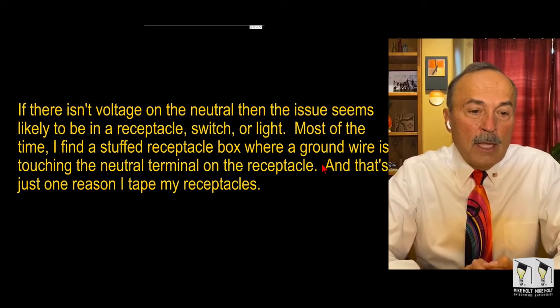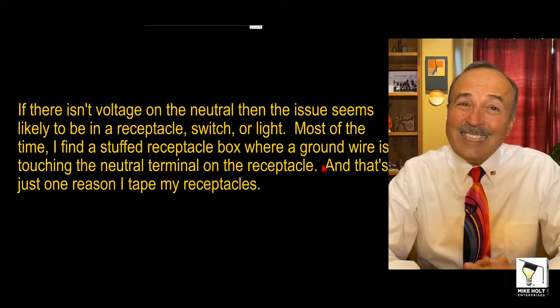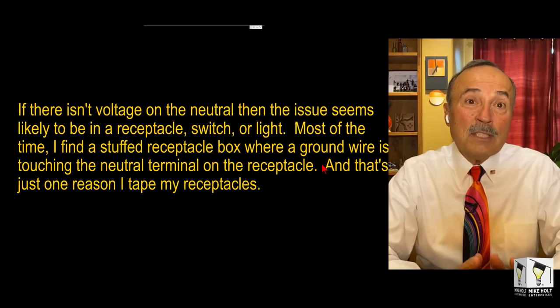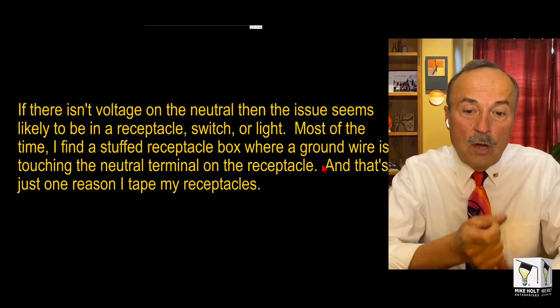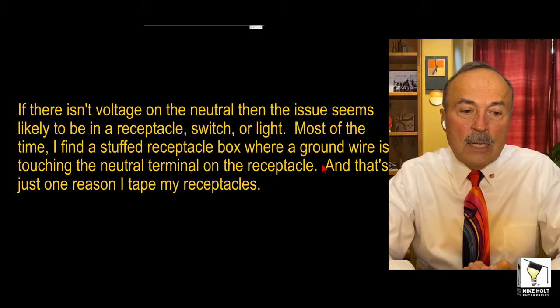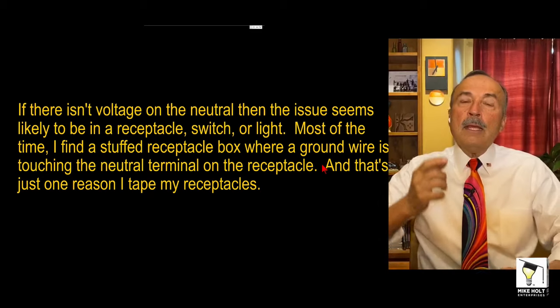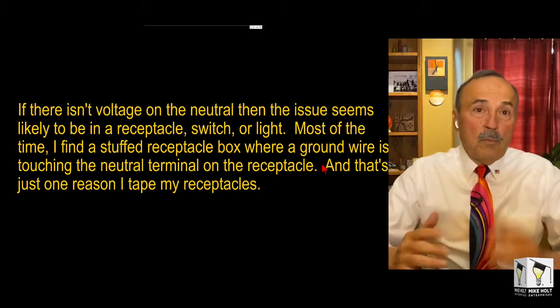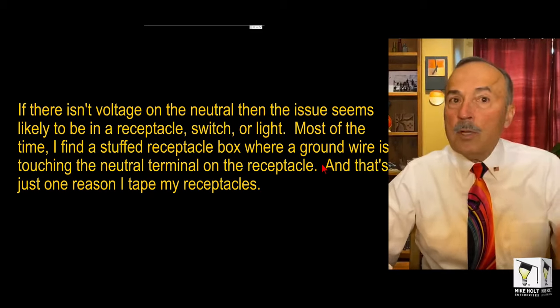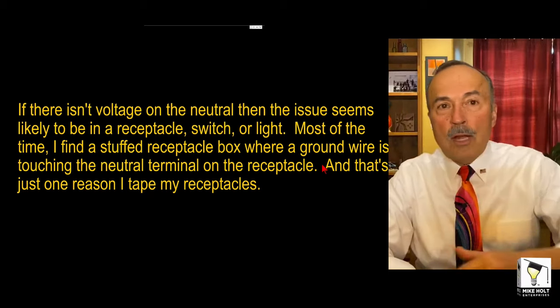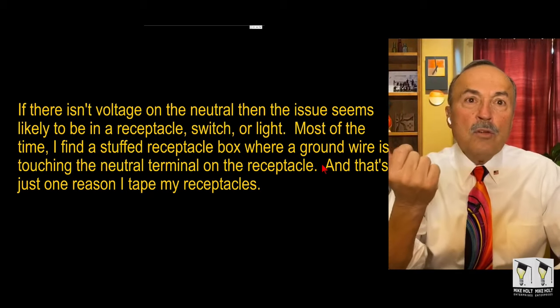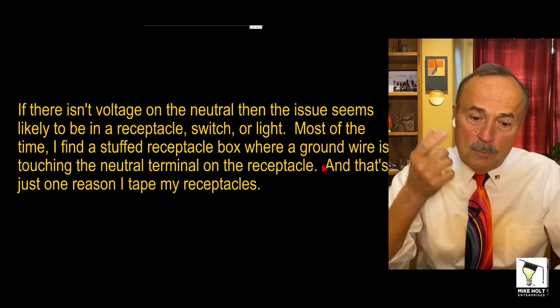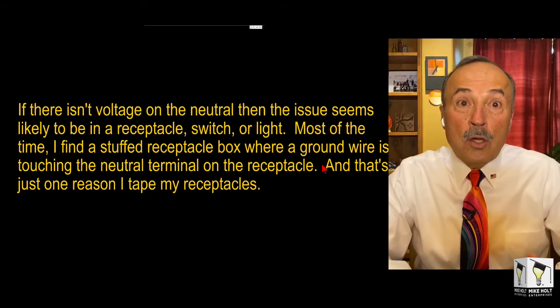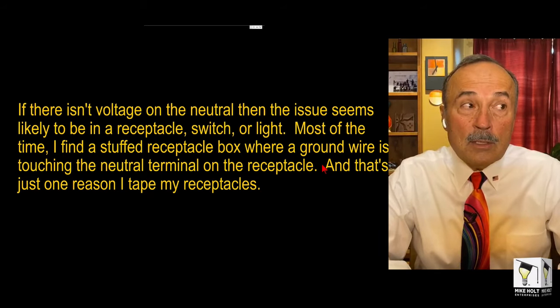And he goes on: if there isn't voltage on the neutral, I don't like that. I would say, if there's not current on the neutral, then the issue seems likely to be in a receptacle, switch or a light. In other words, you're in a remodel job, right? And then you put the AFCI on and it trips. Then you find the neutral associated with that particular phase conductor, put an ammeter on there, and you see no current. Holy crap, it's not sharing.